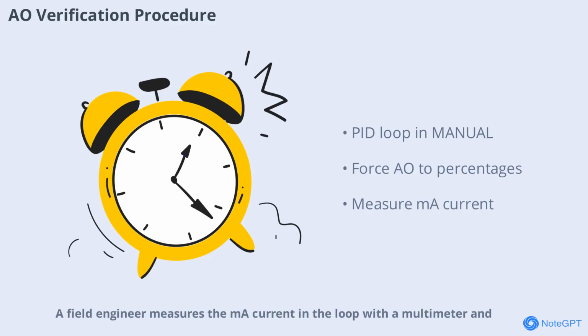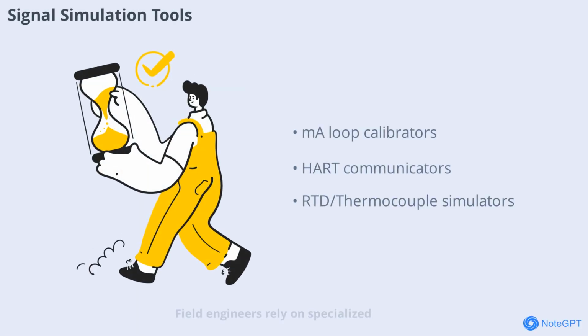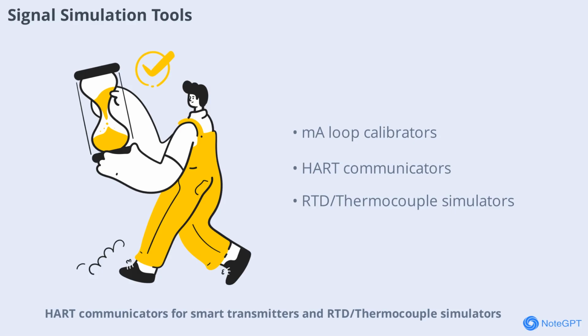A field engineer measures the mA current in the loop with a multimeter and physically confirms that the valve or VFD moves to the correct position or speed. This procedure ensures that analog outputs are accurately mapped and responsive to control commands. Field engineers rely on specialized tools for signal simulation and verification. These include mA loop calibrators like the Fluke 787, HART communicators for smart transmitters, and RTD thermocouple simulators.